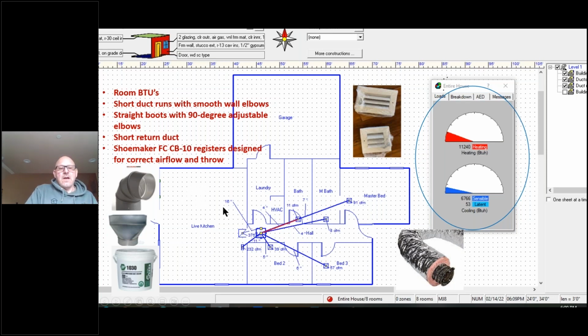So when I design a system, I want to do a short return. The return is right here. I don't think this return is 6 feet away. That's the biggest nemesis in this project, so we want to get that really close. Everything is figured out. We use these Shoemaker FCCB10 registers. We design these registers at a specific size for the amount of airflow. Like for 11 CFM, we use this little 4x4. For this, probably 39 CFM, we'll use like a 4x6. Everything has to have this great throw. So we have this entrainment that Larry was talking about earlier, and I wanted to touch on this also. Entrainment does not work if your airflow, let me see if I can explain this correctly.